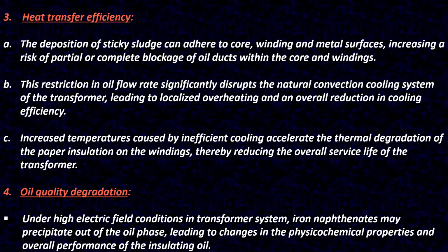Number four, oil quality degradation. Under high electric field conditions in the transformer system, iron naphthenates may precipitate out of the oil phase, leading to changes in the physiochemical properties and overall performance of the insulating oil.